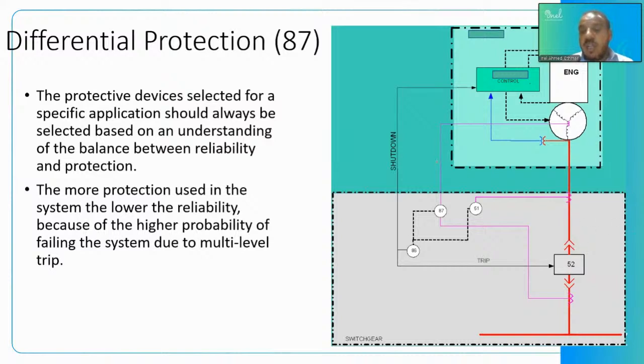Again, it's the same one. We can incorporate the overcurrent protection with other types of protection. So the differential protection can collaborate as a second layer of protection with the overcurrent protection. They can communicate with each other.